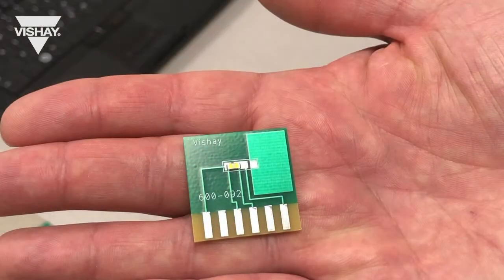Let's take a look at the demo setup. We have two test cards. The first one has a resistor mounted to it that is not connected to the heat sink. The second test card has a resistor mounted to it with a ThermaWick Thermal Jumper connecting it to the heat sink on the test card.